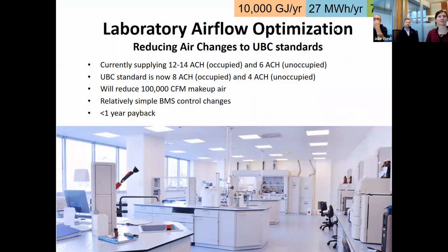The next thing that we looked at in this building is reducing the air changes. Early on in our design process, we had a technical guideline that said we wanted 12 to 14 air changes per hour in occupied and 6 in unoccupied. Through a lot of research and information, we decided to change the UBC standard to 8 air changes during occupied and 4 unoccupied. That's what our new buildings are built at, but this one was still operating at 12 and 14. By changing the air changes to our current standards, we were able to reduce makeup air by roughly 100,000 CFM. This had a less than 1 year payback and fairly substantial energy savings as well. This was all executed in-house with our group, so yeah, Bax Group did all of the implementation for this one.